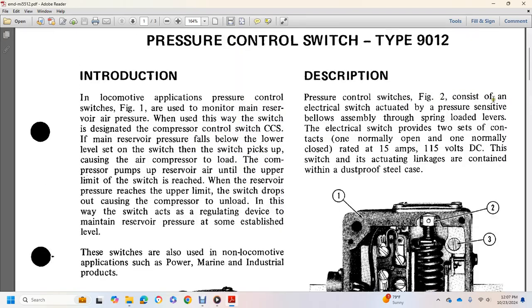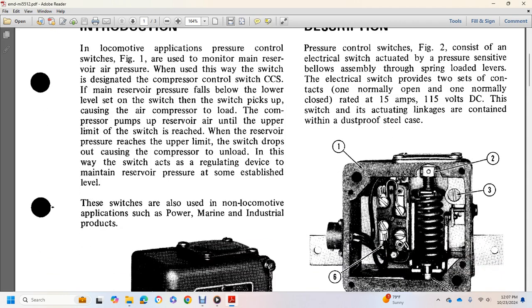Description: pressure control switch, Figure 2. It consists of an electrical switch actuated by a pressure sensitive bellows assembled with a spring-loaded leverage. The electrical switch provides 2 sets of contacts, one normally open, one normally closed, rated at 15 amperes at 115 volts DC. This switch is actuated and the linkage contained within a dust-free steel case.